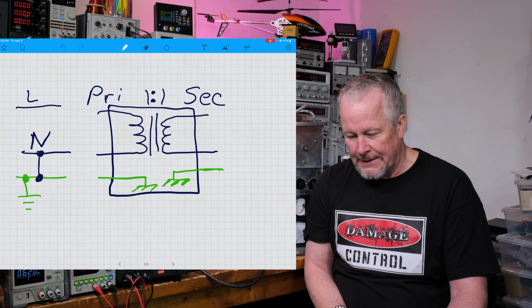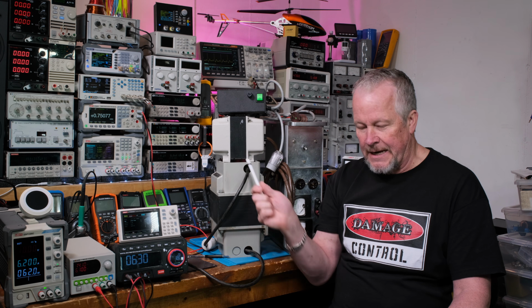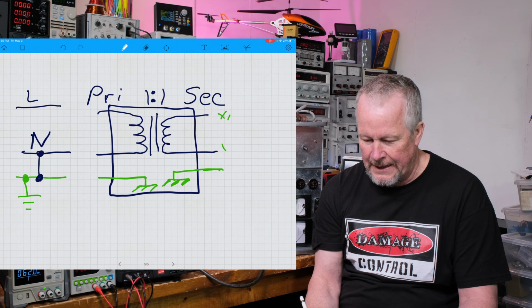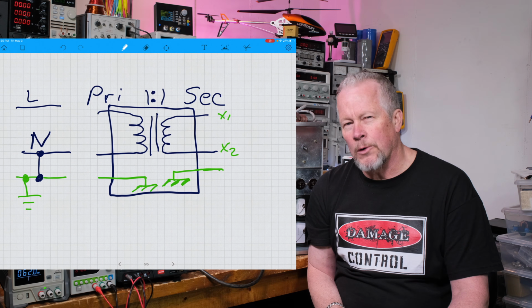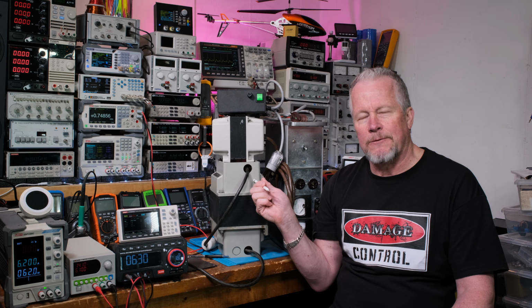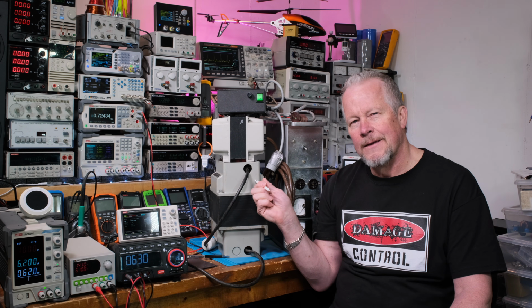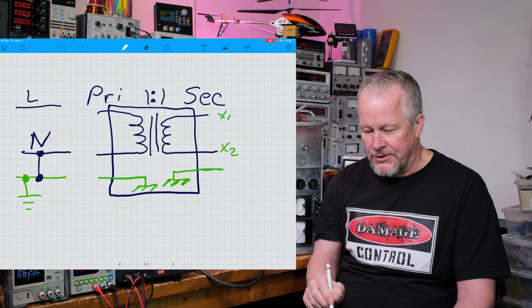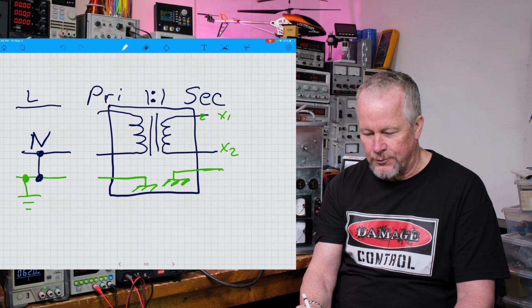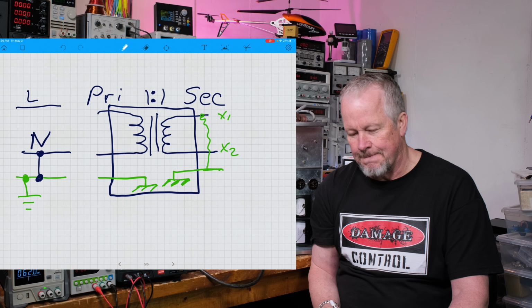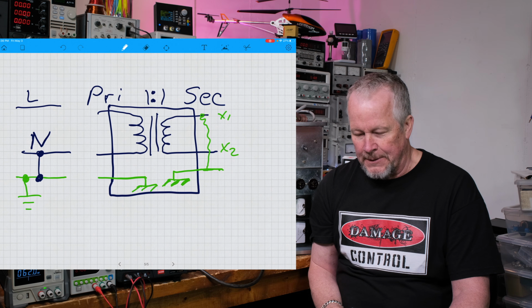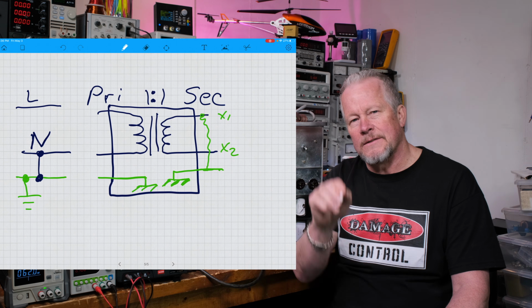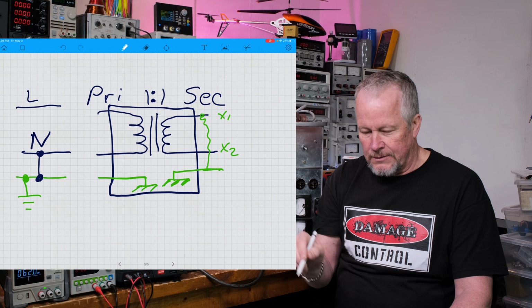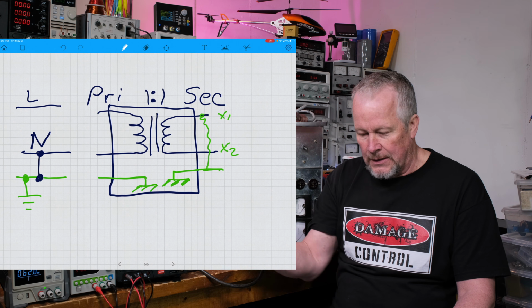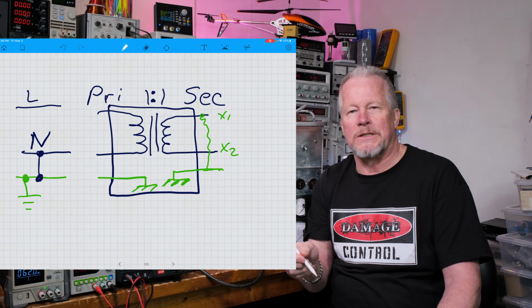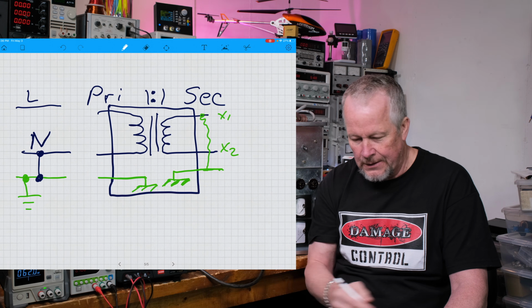Problem is if you have a fault, like say we're going to call it X1, X2. If you have X1 or X2 short to the chassis, what happens? Nothing, because there's no path for current. Let's say X1 gets shorted down here to that chassis. Well, nothing happens because the path through that secondary winding goes out X1, off into your load, comes back to X2 and circles through. Oh, but it also touches your chassis.